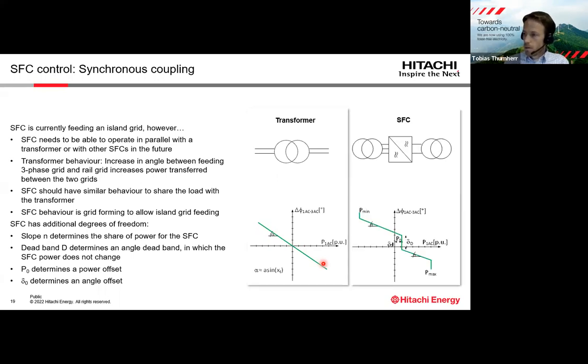Now we want to have a similar behavior of the static frequency converter. So that's why you see here these sloped areas. And there is a discontinuation of the slope on two ends, and this means that the static frequency converter, when it reaches its limit in power, just continues to supply the maximum power. The difference of this slope characteristic compared to a transformer is that we can influence the slope. So we can choose the slope and make the SFC behave as we want it to behave.